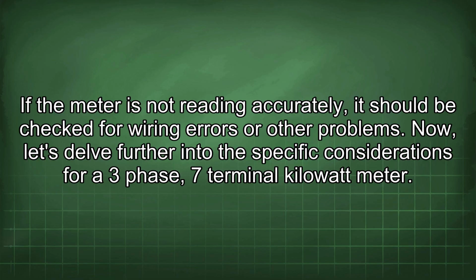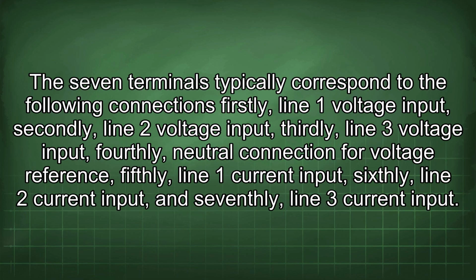Now let's delve further into the specific considerations for a three-phase, 7-terminal kilowatt meter. The 7 terminals typically correspond to the following connections. Firstly, line 1 voltage input. Secondly, line 2 voltage input. Thirdly, line 3 voltage input. Fourthly, neutral connection for voltage reference.